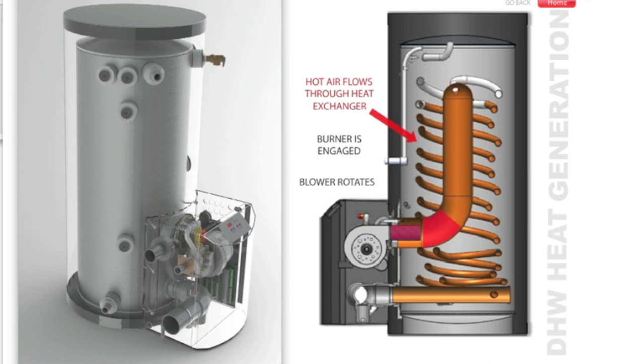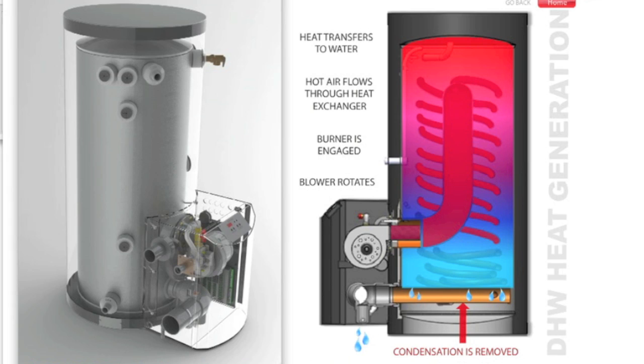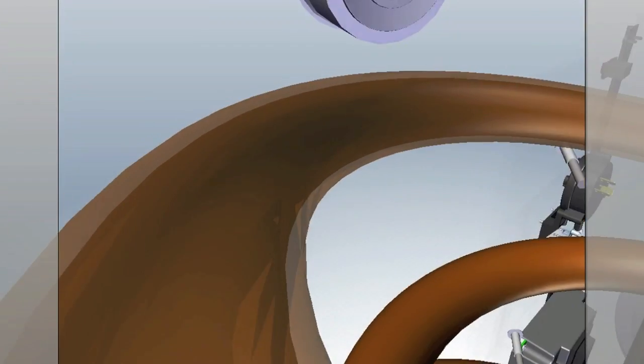This heat exchanger is designed to transfer enormous amounts of energy out of the flue gas channels, which, when complete, transforms the consumed flue gases into a watery acidic mixture that continues down the remaining portions of the heat exchanger and is quickly removed from the appliance to ensure long life.